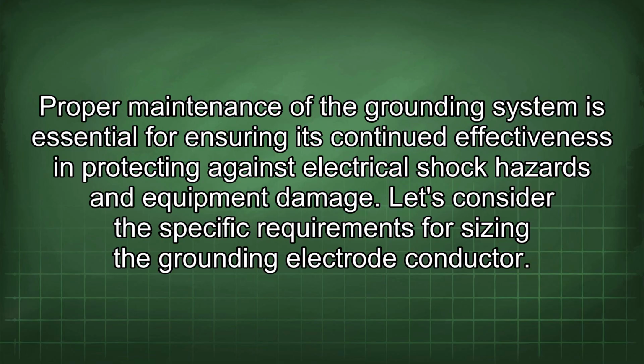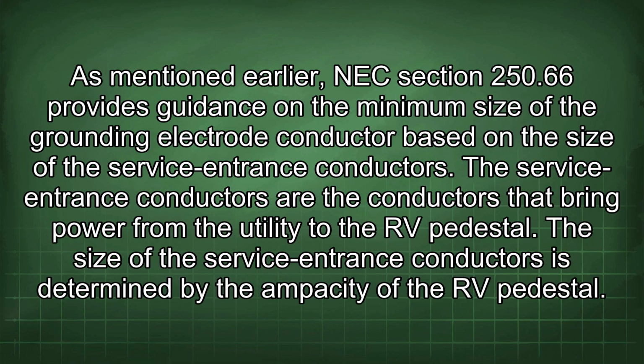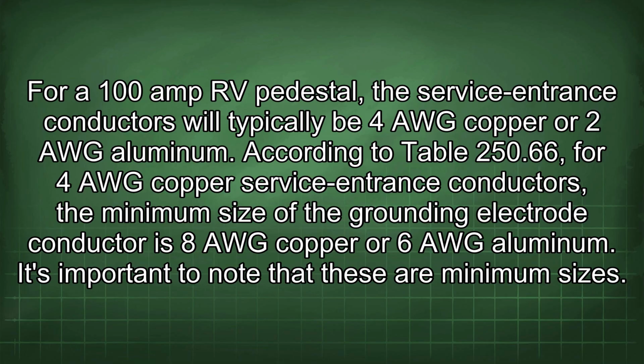equipment damage. Let's consider the specific requirements for sizing the grounding electrode conductor. As mentioned earlier, NEC Section 250.66 provides guidance on the minimum size of the grounding electrode conductor based on the size of the service entrance conductors. The service entrance conductors are the conductors that bring power from the utility to the RV pedestal. The size of the service entrance conductors is determined by the ampacity of the RV pedestal. For a 100 amp RV pedestal, the service entrance conductors would typically be 4 AWG copper or 2 AWG aluminum.